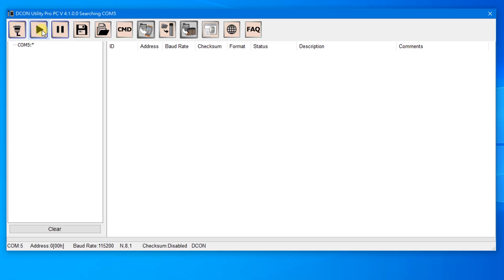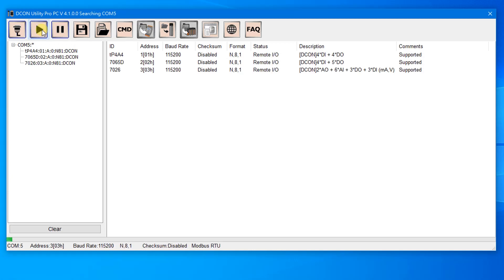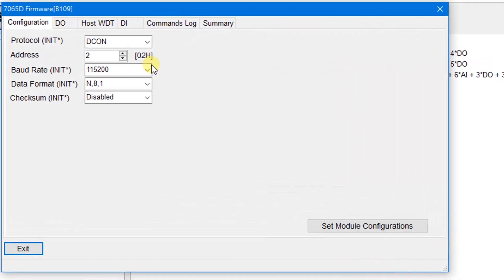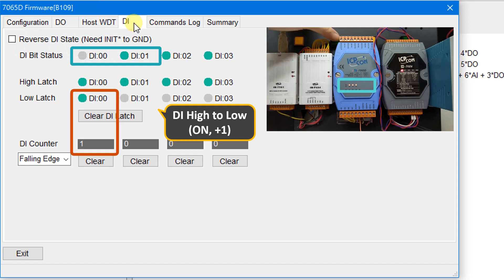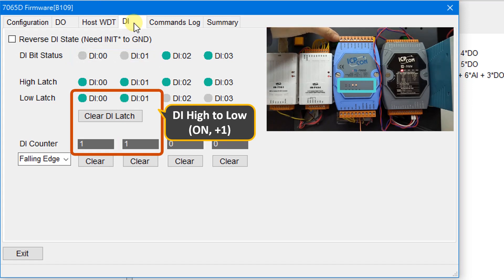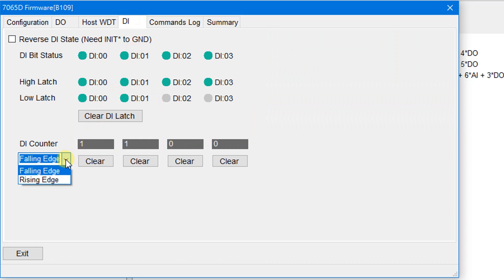Search the IO modules and stop searching when modules are found, then enter the I7065D window. On the DI page, all DI statuses are ON by default — click the button to set them to OFF. The Low Latch indicates that a signal transition from high to low will be latched, and the counter value will increment by one. The DI counter can be set to the falling edge or the rising edge.